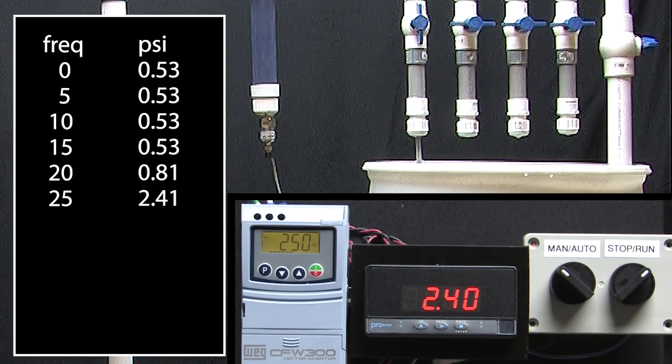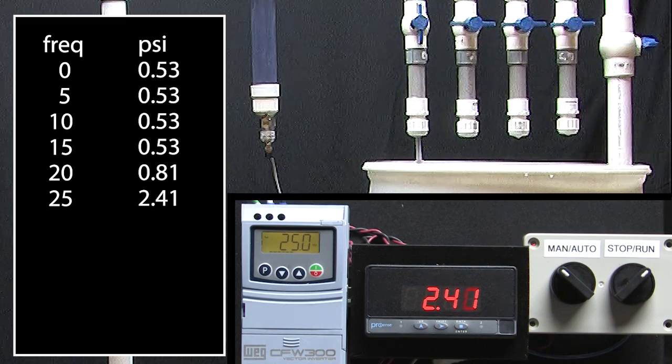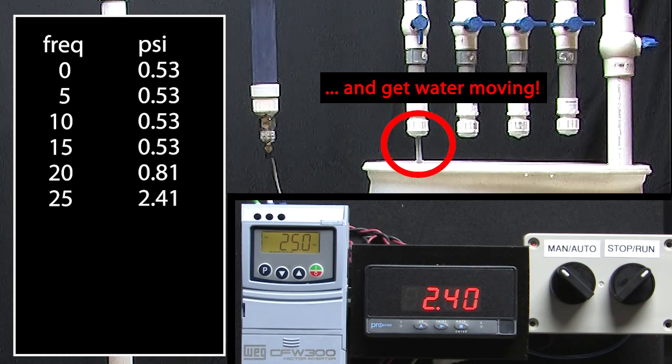A centrifugal pump needs some minimum speed to operate, right? For our system, it takes around 20 Hz to pump enough water to build up any back pressure.